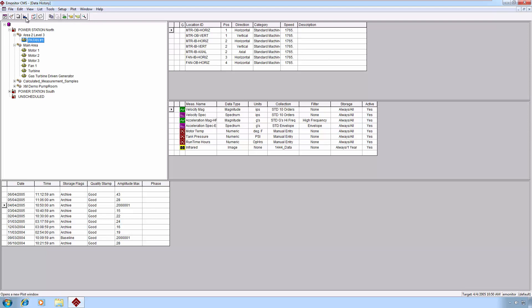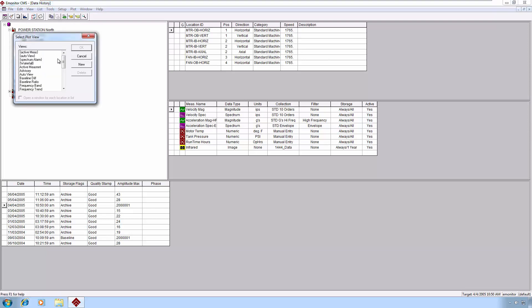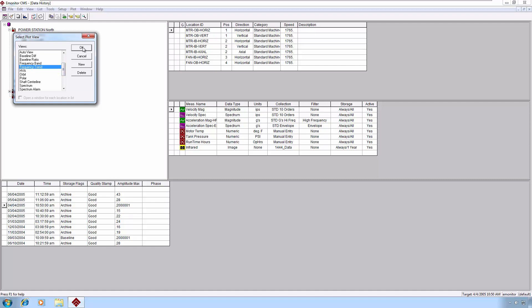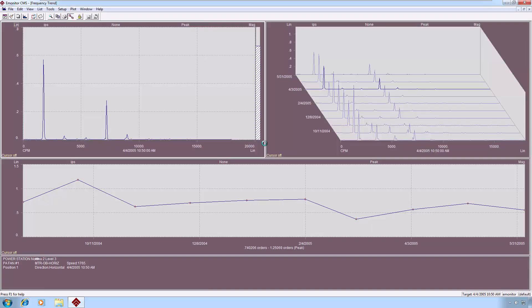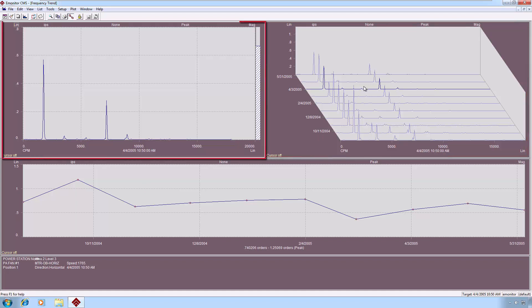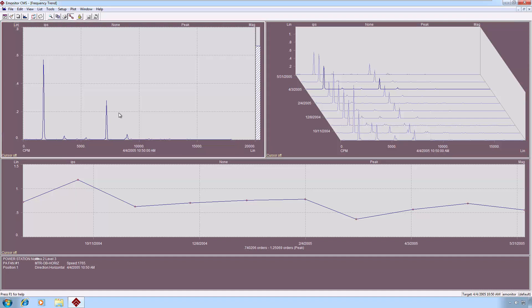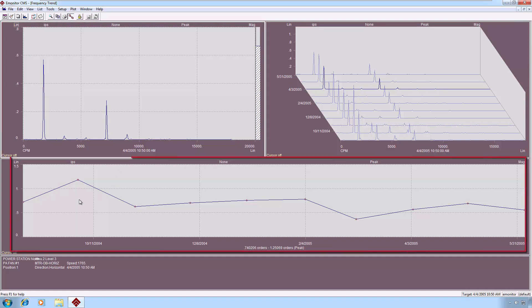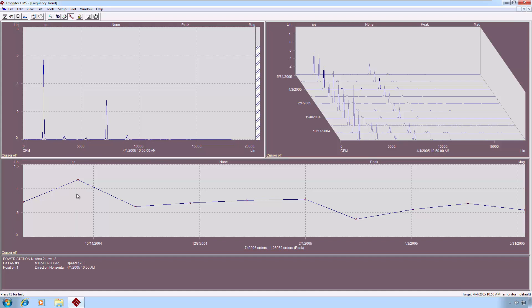Going back to our plot selection, let's look at frequency trend. This is a pretty interesting plot view, a very powerful tool here for the vibration analysts in the group. In addition to having our waterfall in the upper right-hand corner, and then the active cursored spectraplot in the upper left-hand corner, on the bottom pane what we actually have is a dynamically calculated trend of the energy in a dynamically specified frequency band.